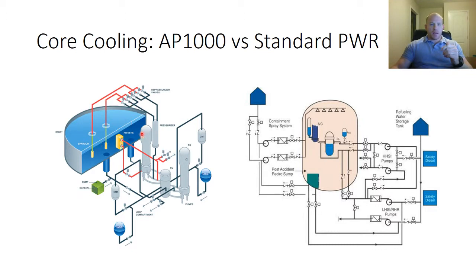It's located higher than the reactor vessel, and once the system is depressurized fully to atmosphere, this tank will use gravity to force inject water over there and keep the core covered. This layout replaces the low head safety injection pumps and associated piping and tanks. Okay.